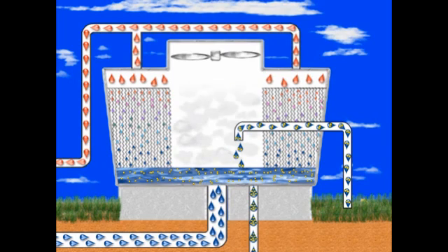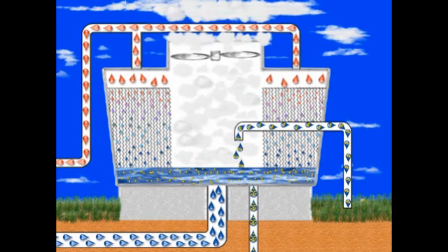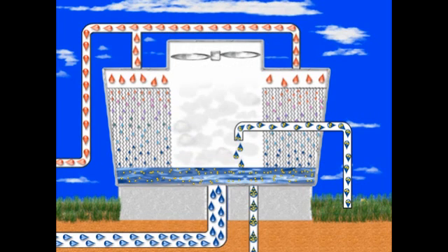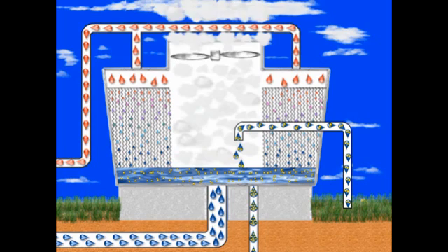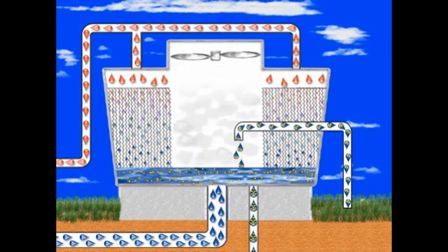Because makeup water carries fewer elements than the system water, it will slowly reduce system concentration. During normal operation, evaporation, bleed off, and makeup are balanced to maintain the proper water volume while creating a continuous open loop.